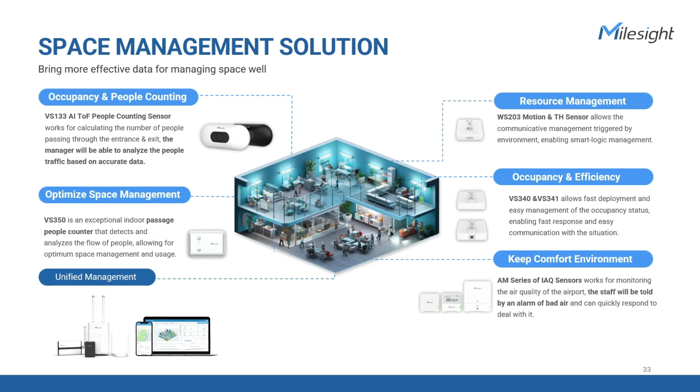Occupancy sensors also help keep the energy consumption for lighting and HVAC systems in commercial buildings in line with energy regulations. For example, HVAC systems are sized for the maximum quantity of occupants in a space, but this full performance isn't necessary when a space hasn't reached its maximum capacity. By using occupancy sensors and people counting sensors, you can collect real-time data on space use and automate HVAC systems to only work as hard as is necessary to provide proper ventilation and ideal temperatures.